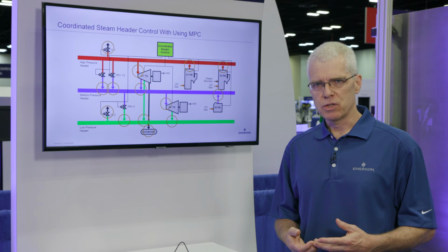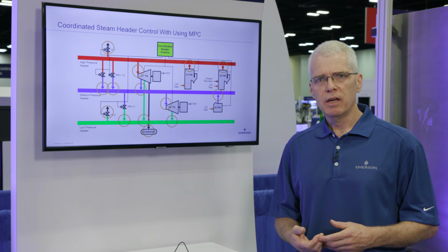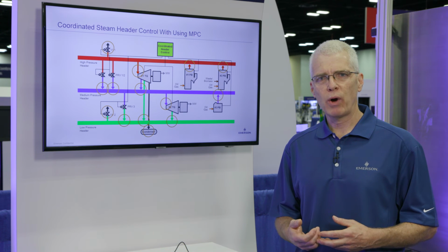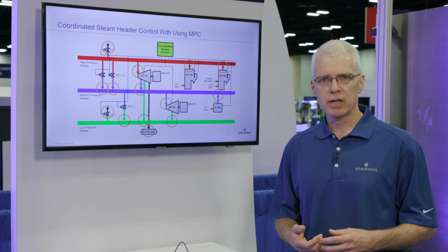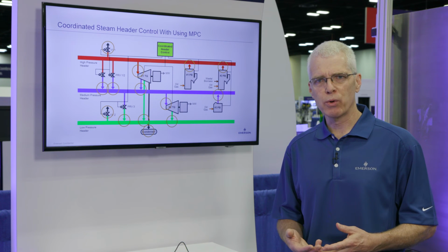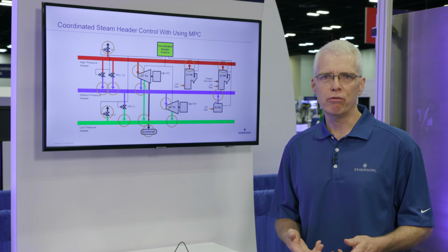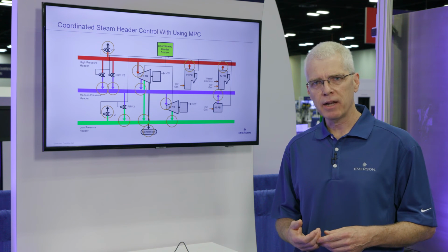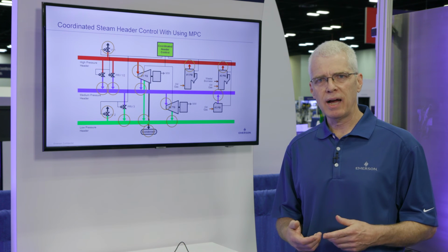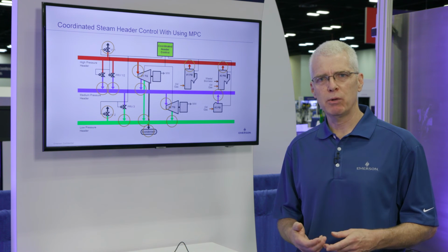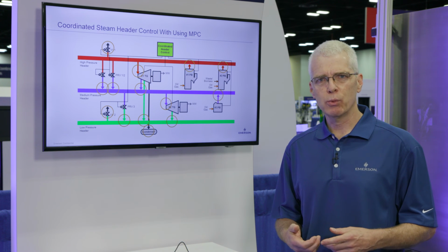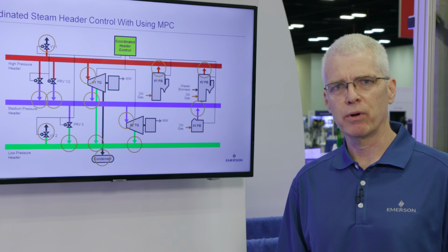One beauty of MPC is its ability to deal with constraints. In a complex steam system, it's easy to arrive at a situation where a turbine section, PRV, or boiler is constrained and cannot be called upon to move faster or move more. These situations can be managed automatically with the MPC approach. The model knows at all times which combination of moves can best be made within limits to first recover from an upset and then to eventually rebalance in the most cost-effective operating scenario.